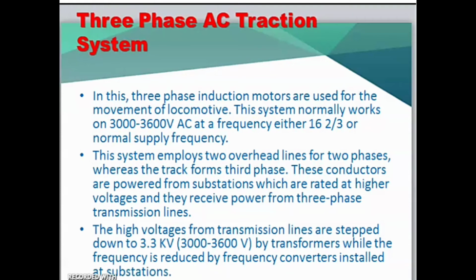This system normally works on 3000 to 3600 volt AC at a frequency of either 16 2/3 Hz or the normal supply frequency. This system employs two overhead lines for two phases, whereas the track forms the third phase. These conductors are powered from substations which are rated at higher voltages, and they receive power from three phase transmission lines. The high voltage from the transmission lines is stepped down to 3.3 kV, that is 3000 to 3600 volt, by a transformer, while the frequency is reduced by frequency converters installed at the substations.